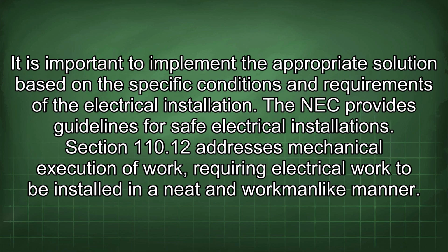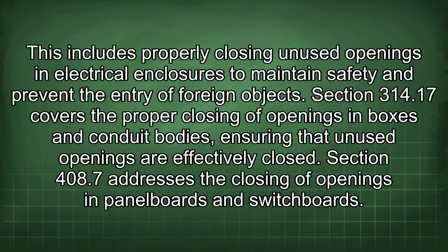The NEC provides guidelines for safe electrical installations. Section 110.12 addresses mechanical execution of work, requiring electrical work to be installed in a neat and workmanlike manner. This includes properly closing unused openings in electrical enclosures to maintain safety and prevent the entry of foreign objects. Section 314.17 covers the proper closing of openings in boxes and conduit bodies, ensuring that unused openings are effectively closed. Section 408.7 addresses the closing of openings in panel boards and switchboards.